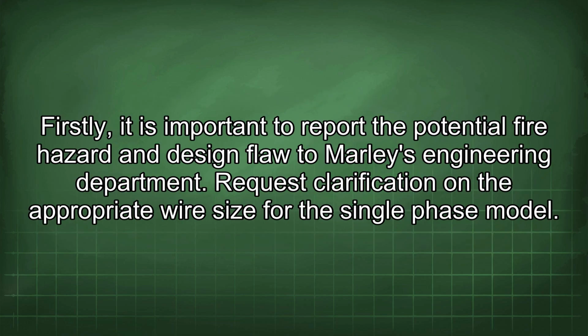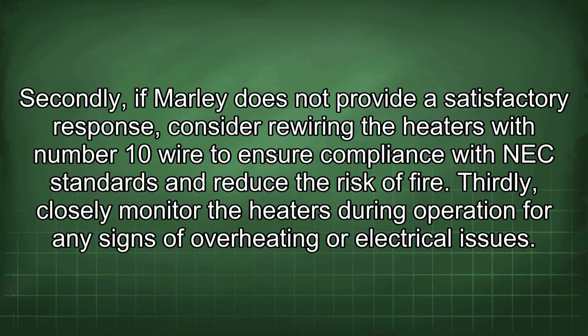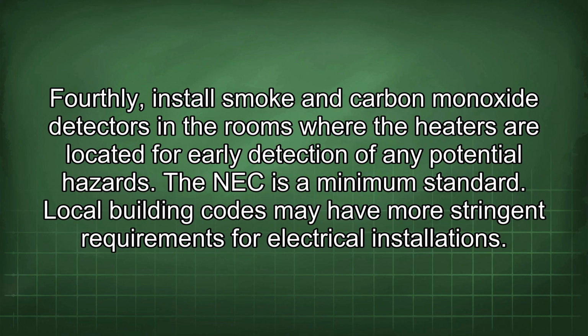Firstly, it is important to report the potential fire hazard and design flaw to Marley's engineering department. Request clarification on the appropriate wire size for the single-phase model. Secondly, if Marley does not provide a satisfactory response, consider rewiring the heaters with number 10 wire to ensure compliance with NEC standards and reduce the risk of fire. Thirdly, closely monitor the heaters during operation for any signs of overheating or electrical issues.